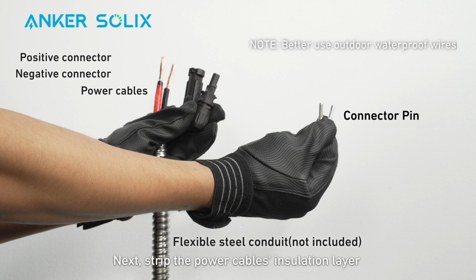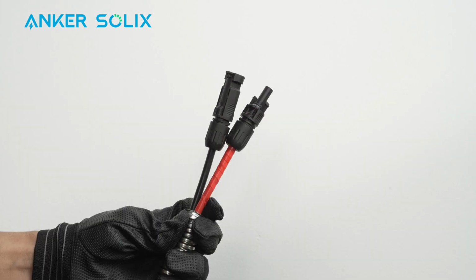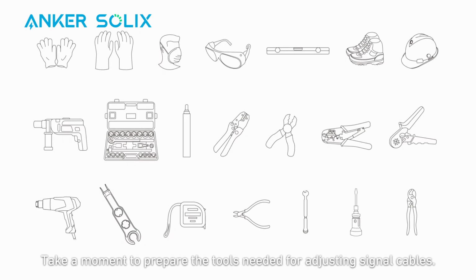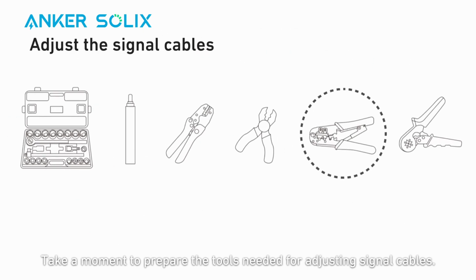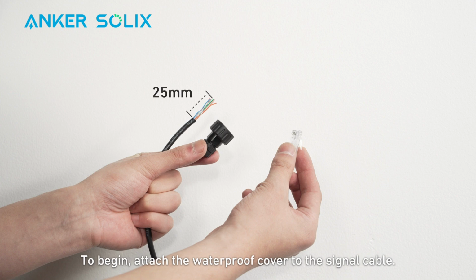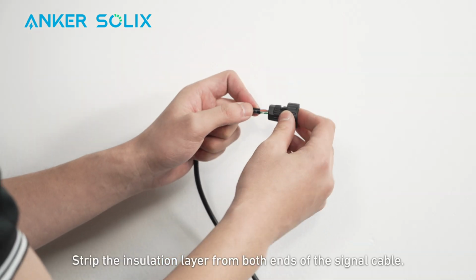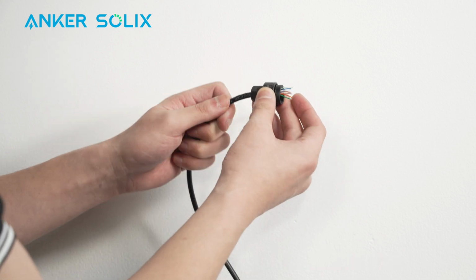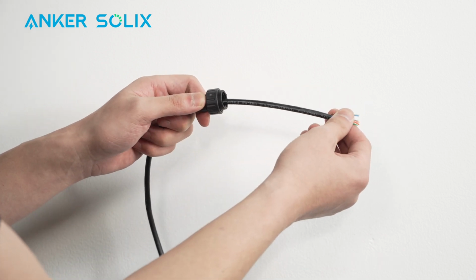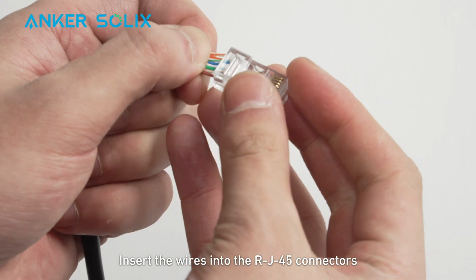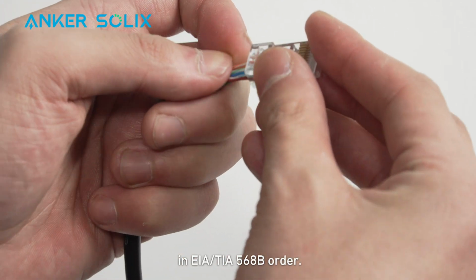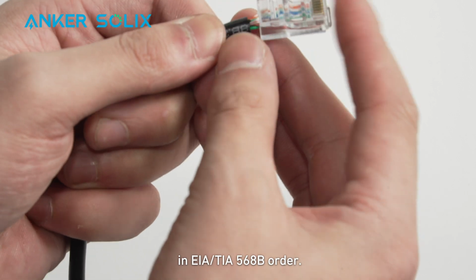Next, strip the power cable's insulation layer and route them through a flexible steel conduit. Attach the connector to the power cables. Take a moment to prepare the tools needed for adjusting signal cables. To begin, attach the waterproof cover to the signal cable. Strip the insulation layer from both ends of the signal cable. Insert the wires into the RJ45 connectors in EIA/TIA 568B order.